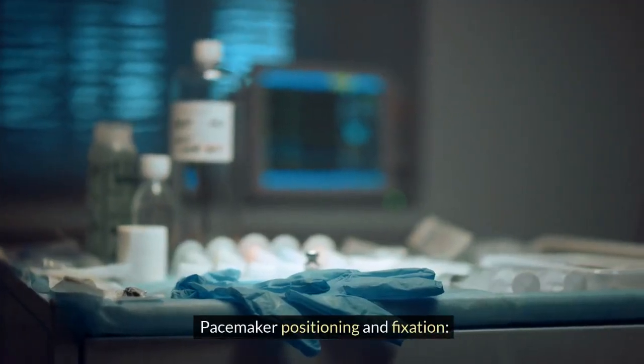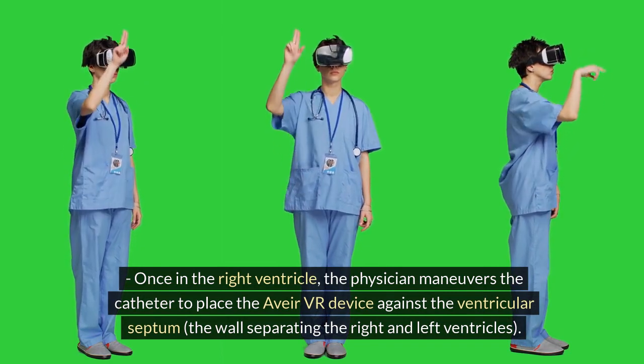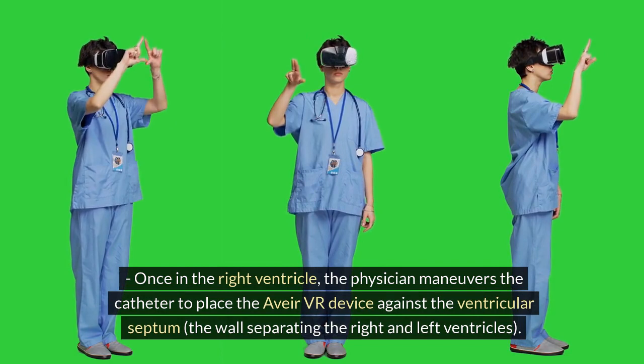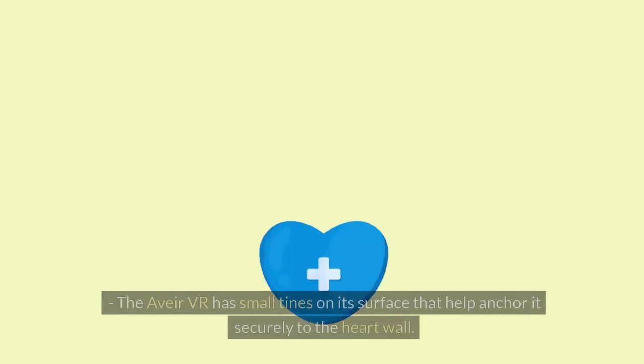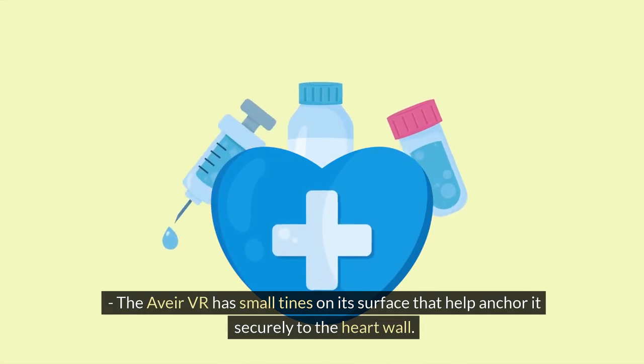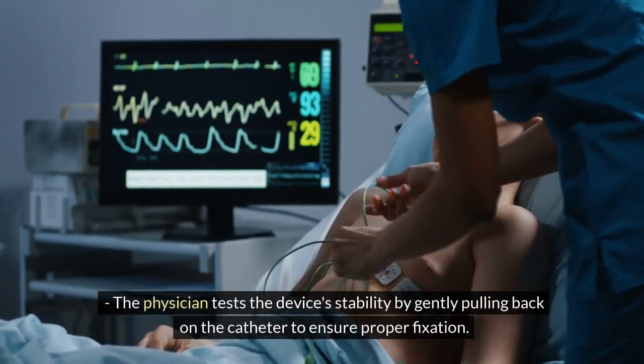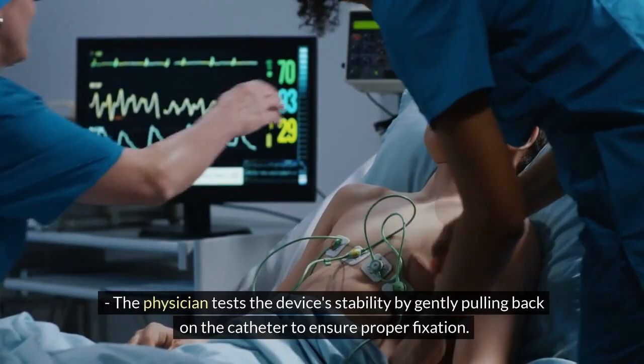Step 4: Pacemaker positioning and fixation — once in the right ventricle, the physician maneuvers the catheter to place the Aveir VR device against the ventricular septum, the wall separating the right and left ventricles. The Aveir VR has small tines on its surface that help anchor it securely to the heart wall. The physician tests the device's stability by gently pulling back on the catheter to ensure proper fixation.